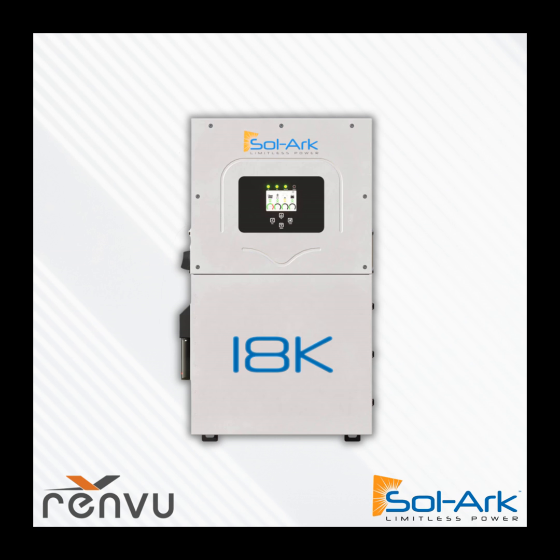Do I need two 15Ks or is one enough? One 15K is just enough for whole home backup. At 18 kilowatts, what I think about is the size of the generator industry when they say this is a home backup generator - they're talking about generators in the 22 to 26 kilowatt range. Maybe those generators at most run at 75% efficiency, which is right in the range of the 18K. So the 18K, for reasons we'll dive into in the spec sheet, is a large enough inverter where you don't really need to worry about the design.